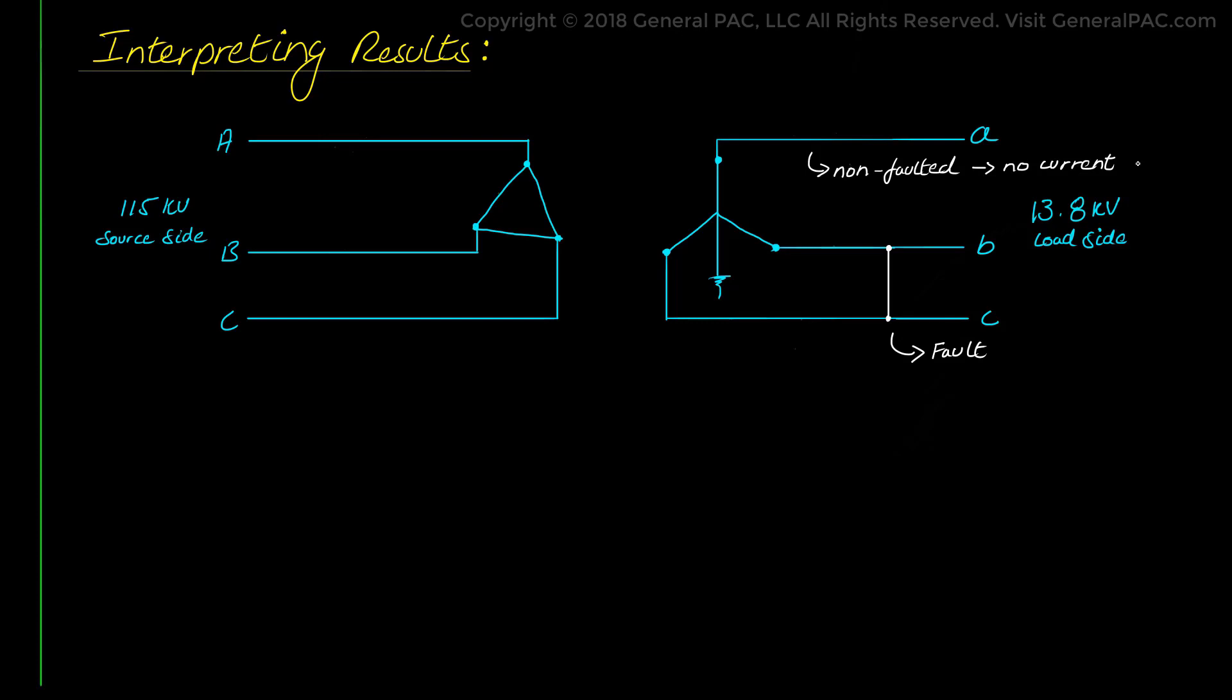Now when it comes to voltage quantities at the point of the fault, we proved by hand that phase A voltage at the point of the fault on the 13.8 kV system is the normal operating quantity, meaning that it is 13.8 kV/√3, it is 7.96 kV phase voltage.